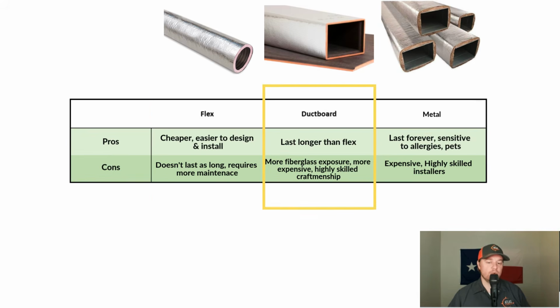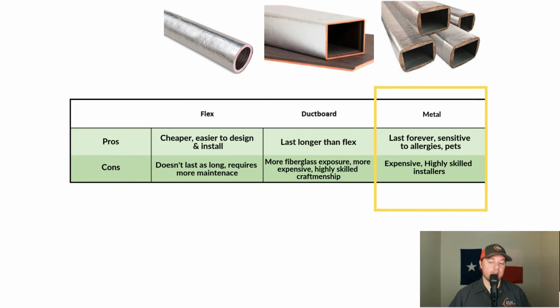When it comes to ductboard, it does have a longer life than flex. However, it is more expensive and requires more attention to design and craftsmanship. When it comes to metal, it can last for a really long time. It's essentially commercial grade ductwork and is great for people who are sensitive to allergies and pets because you can have it cleaned on a routine basis without damaging anything. Now, metal is going to end up costing 3 to 4 times as much as flex ductwork. You have to pay a huge amount of attention to the design and workmanship, along with keeping an eye on the insulation wrap.